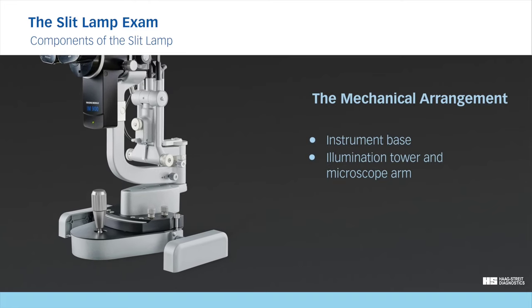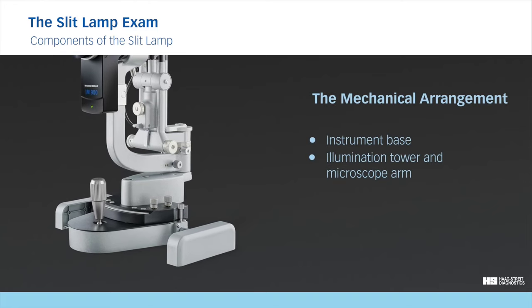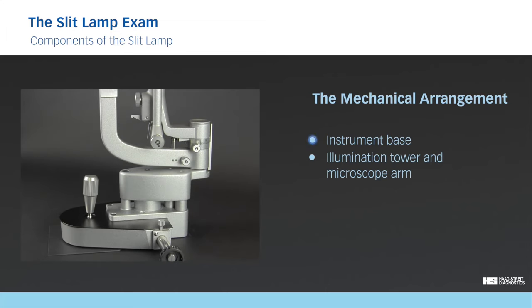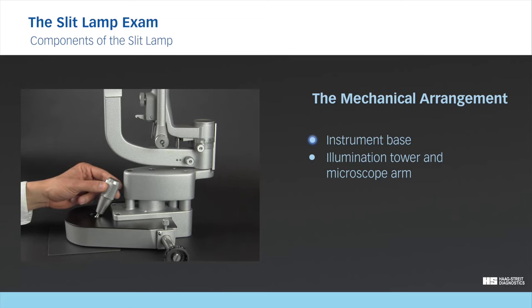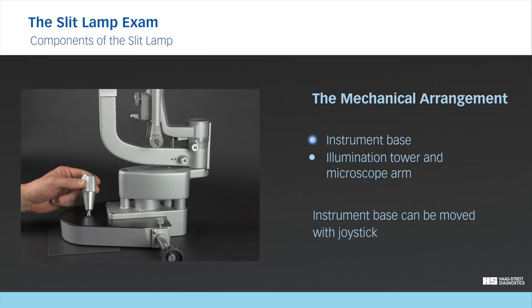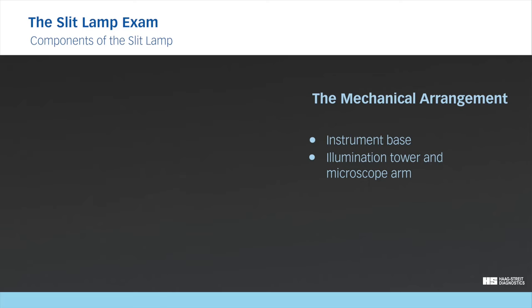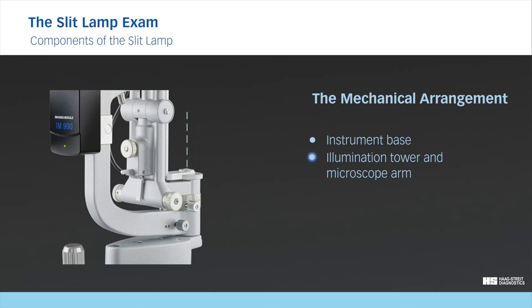The mechanical arrangement consists of the instrument base that supports the illumination tower and the microscope arm. The instrument base provides the platform to position the slit lamp in front of the patient and to control focus. The fine three-dimensional movements during the examination are controlled with the joystick. The illumination tower and the microscope arm share a common pivot. In normal use, the focus of the slit beam and that of the microscope are at the same point.